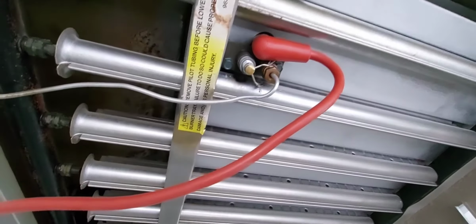Oh, so the reason why I have the main valve disconnected is that I don't want, while this thing is out and in my hand, the sensor to finally decide to read the flame and then open the nozzles. That could be really bad, right? So the main valve is disconnected. Only the pilot valve, which is this little tube right here, is connected.